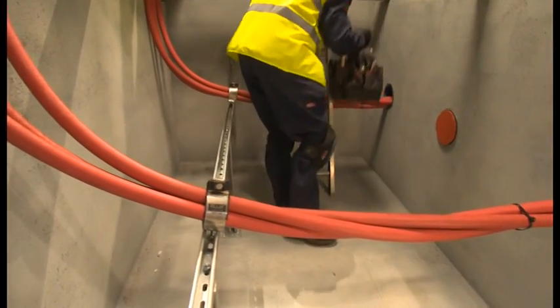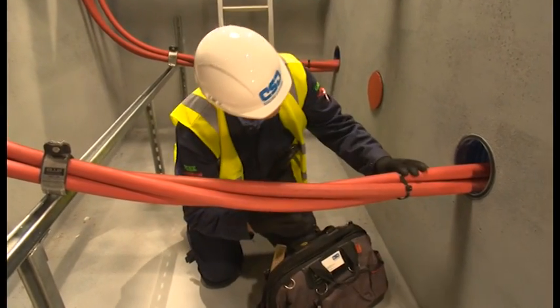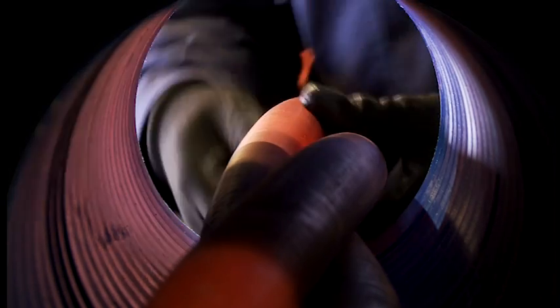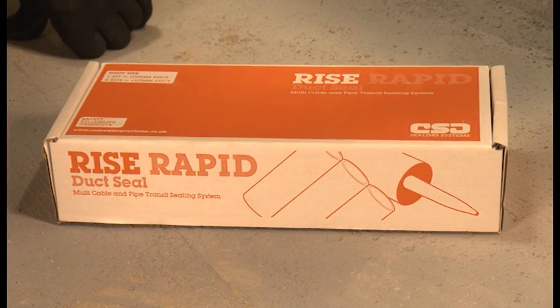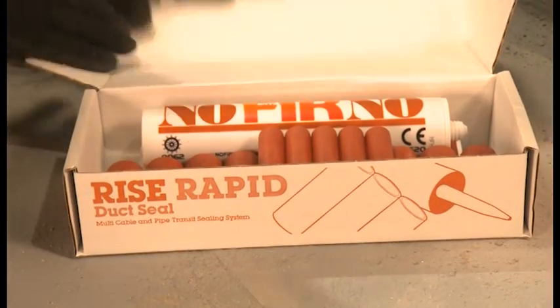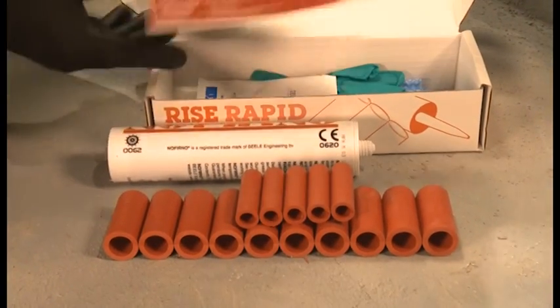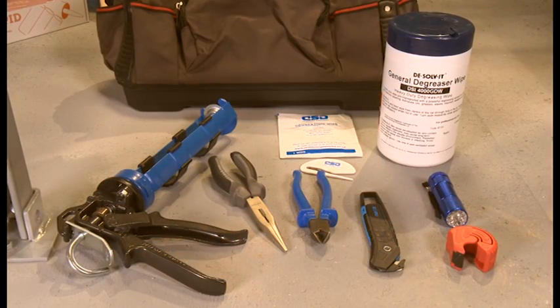Let's take a look at the installation of the product in a typical substation pit environment. We're going to seal a 150mm duct containing 37mm cables in trefoil formation. Nofirno filler sleeves and sealant come in pre-packed kits to suit popular sized ducts. One standard kit will seal a typical 100mm duct and two kits will be needed for a 150mm one. Other kit sizes are available and the system can be used in any sized or shaped duct.